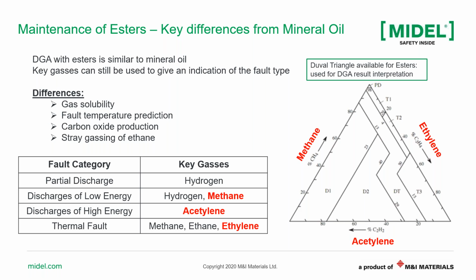Now, DGA with esters is still very similar to that of mineral oil. In DGA, we emphasize, one, we need to observe the trending. Second, we need to have good sampling procedures, so as to prevent any contamination. And so in esters, we follow the same procedures as mineral oil. And there are key differences between esters and mineral oil. The first is the gas solubility, because esters have different chemical structure than mineral oil, so gases will be soluble in different ratios or percentages.